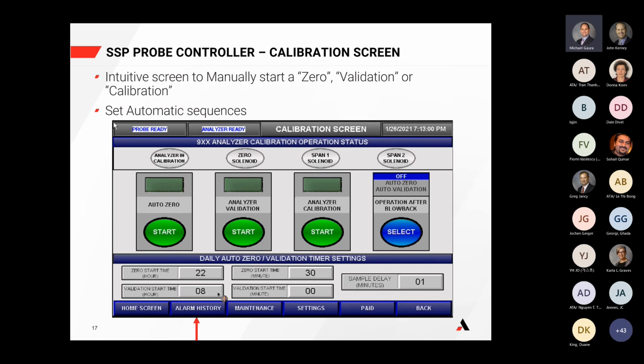A validation is not a calibration; it's just running a known sample through the assembly and ensuring that the analyzer is measuring as intended. Again, it's a test system. No adjustments are made to any of the parameters of the analyzer.